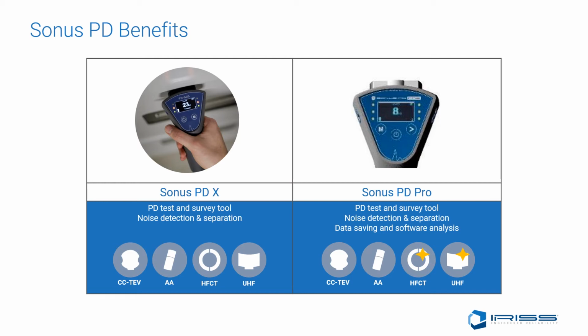Partial discharge activity inside metal-clad high-voltage assets induces a small voltage impulse called Transient Earth Voltage along the surface of the metal panels. TEV travels around the surface to the outside of the switchgear, where it can be picked up externally using the Sonus PD Pro and Sonus PDX.